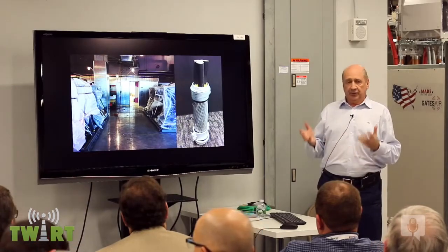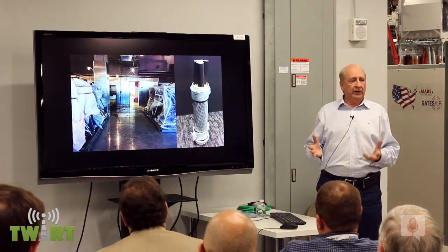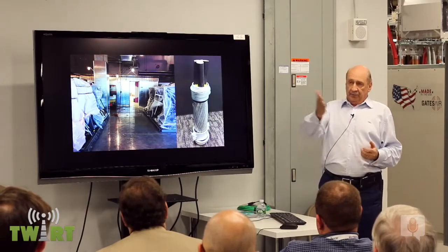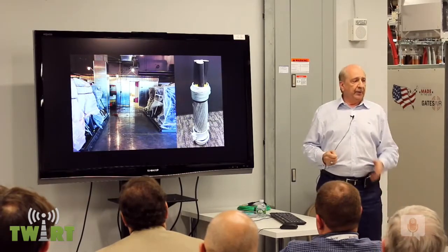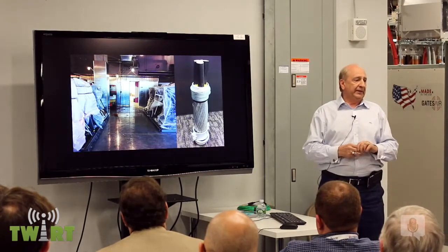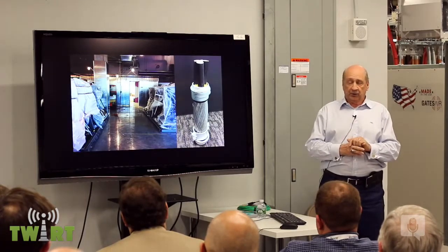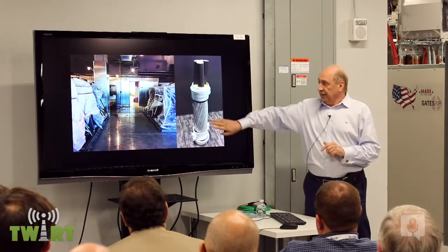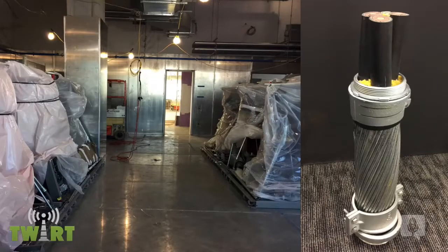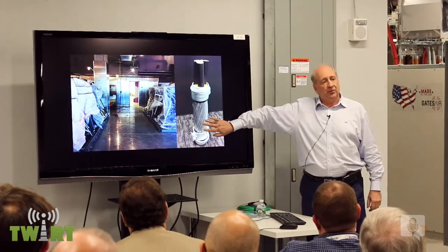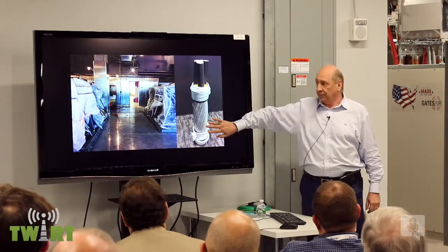Part of that effort was to bring the power up here in a useful, non-wasteful method. So everything being 480, we didn't bring 480 up from the street. We brought it up at 13.8 kilovolts. And we're actually converting it to 480 on the floor. So that's a 13.8 feed. There's two of those, primary and a backup feed coming up the building. That's the feed. If we did it at 480, we'd have 20 of those in each riser closet to get the same power up here.